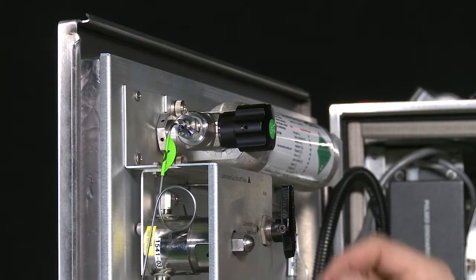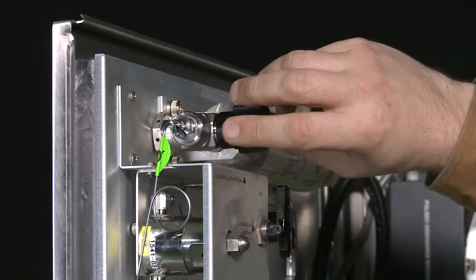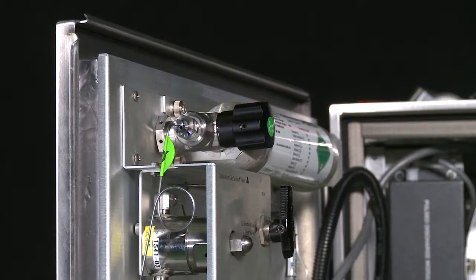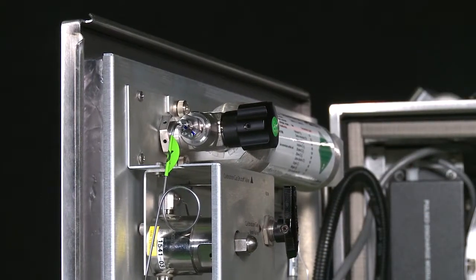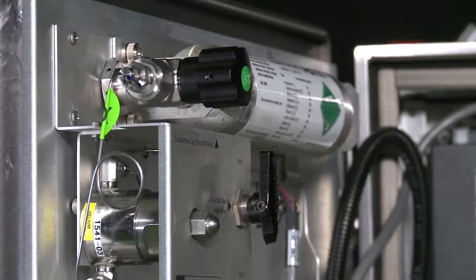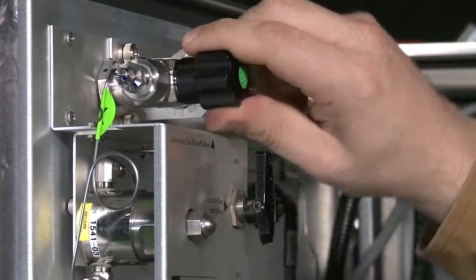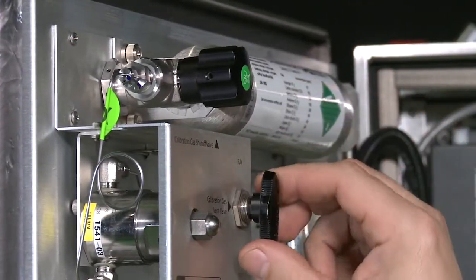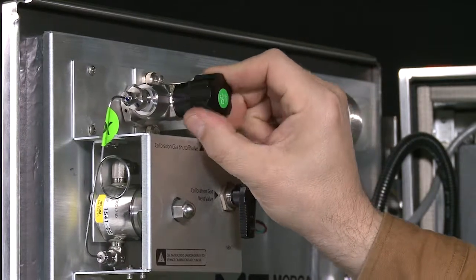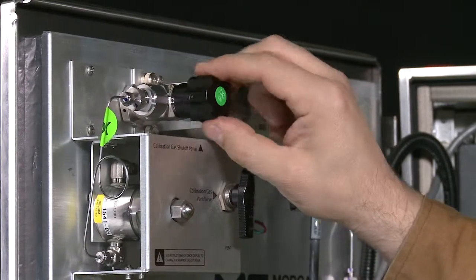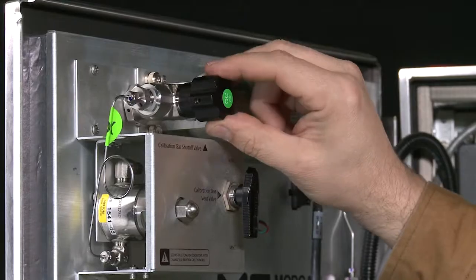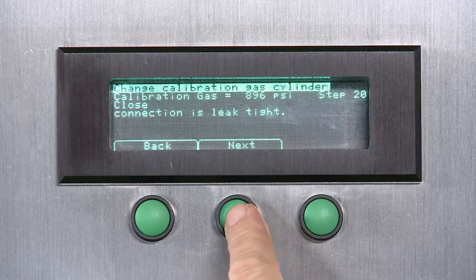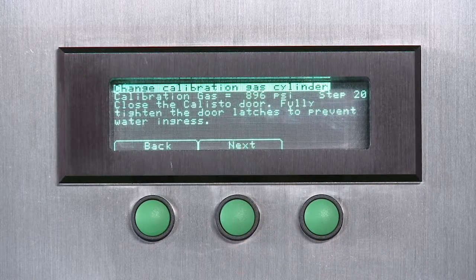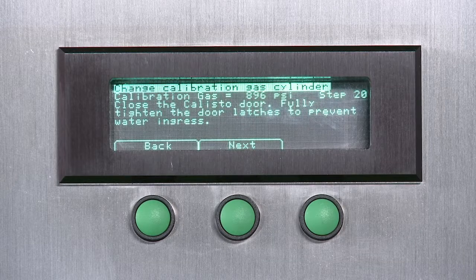Open the calibration gas shutoff valve 1/4 of a turn and reclose as quickly as possible. Wait 5 seconds for the gas to escape. Repeat the previous step a second time, then turn the vent valve to run. Open the calibration gas shutoff valve about 1 full turn. Verify that the calibration gas pressure is at least 800 psi. If not, contact Morgan Schaffer.